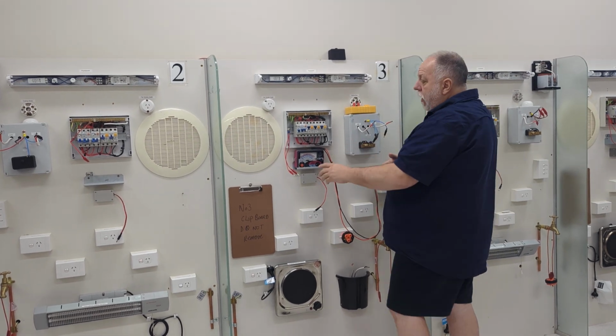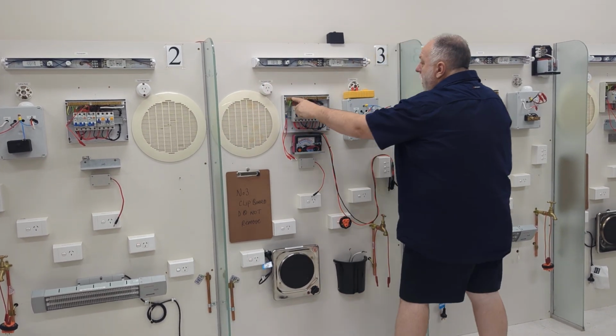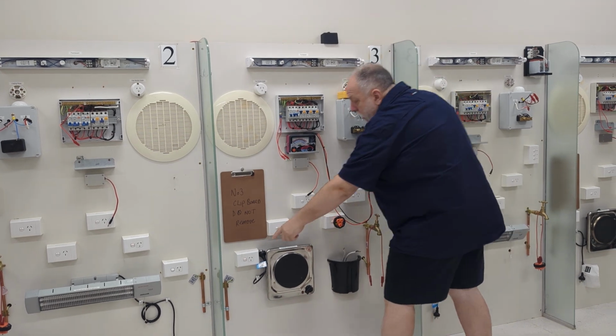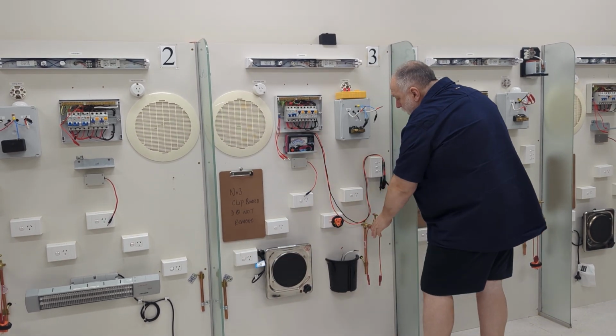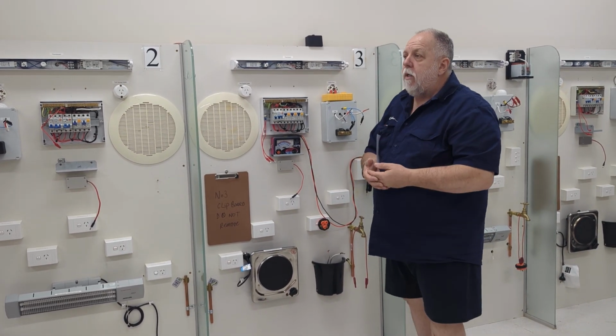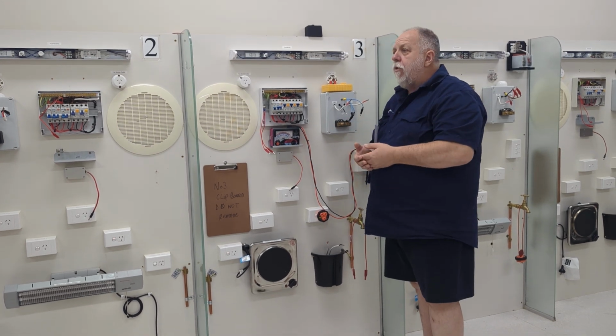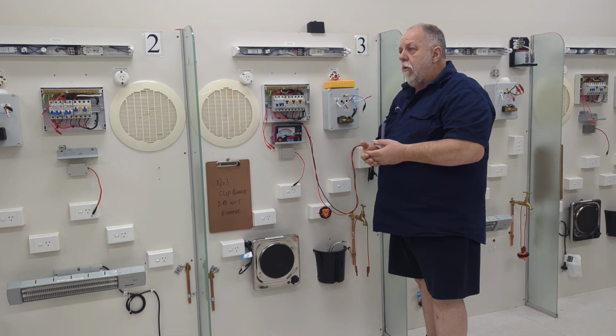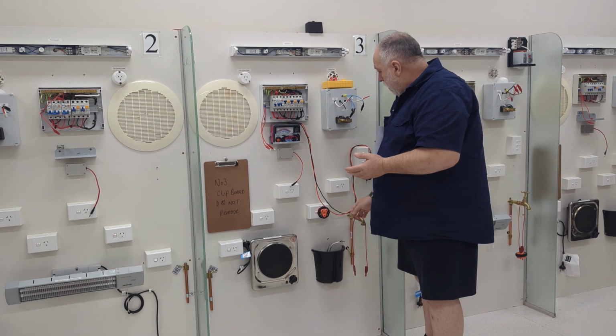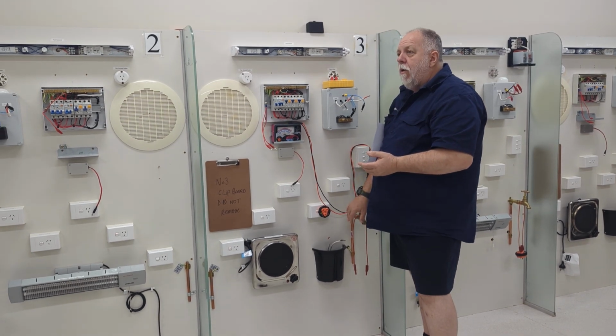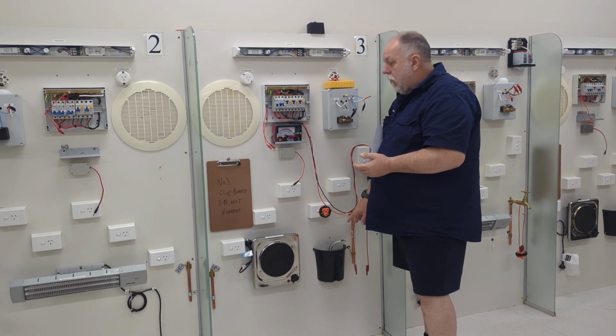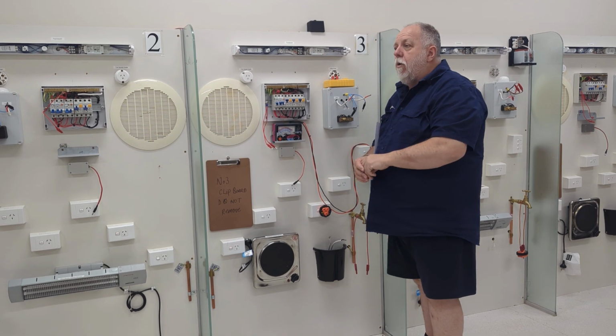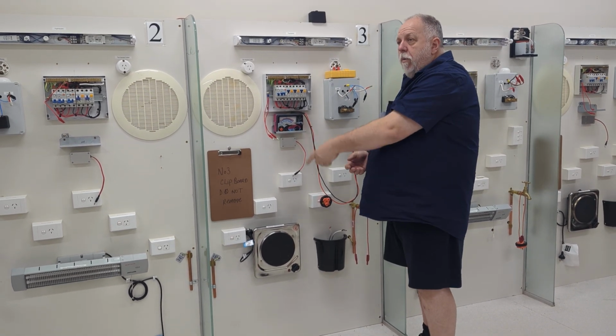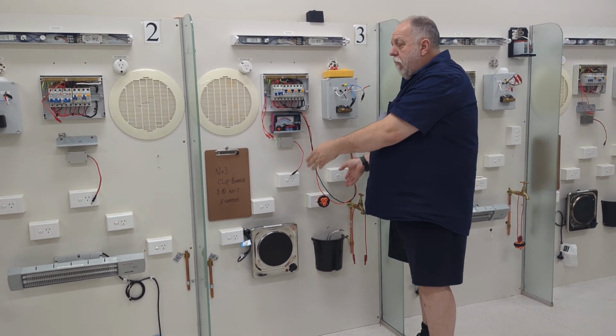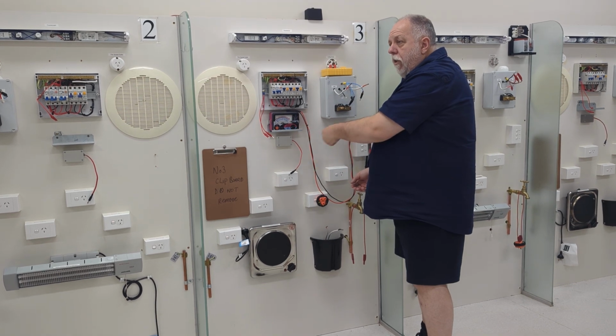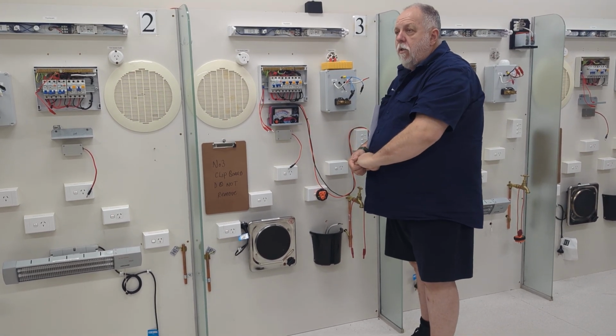The main earthing conductor, right, which we have from here down to this one down here, the earth electrode. Then we have a bonding conductor. A bonding conductor and the main earth are two different cables, all right? I get people sometimes saying, oh, I'll run the main earth to the tap because it looks like a bonding conductor and then going to the main earth. You can't. You've got to go from the main earth, right? Either run them separately or you go to the main earth first, then to the tap. Does that make sense? Yes or no?